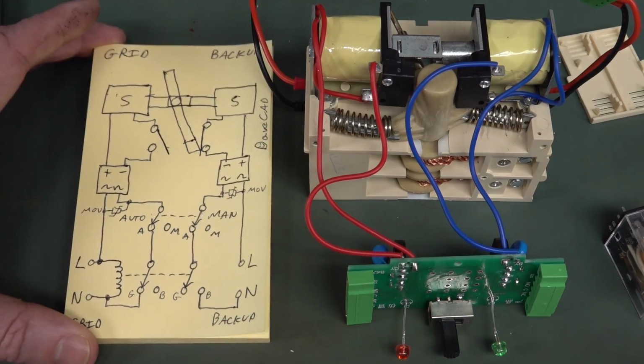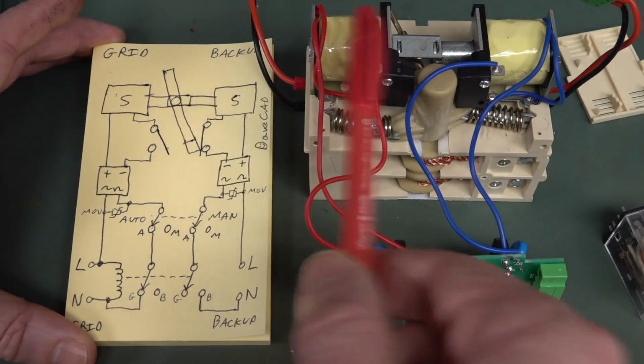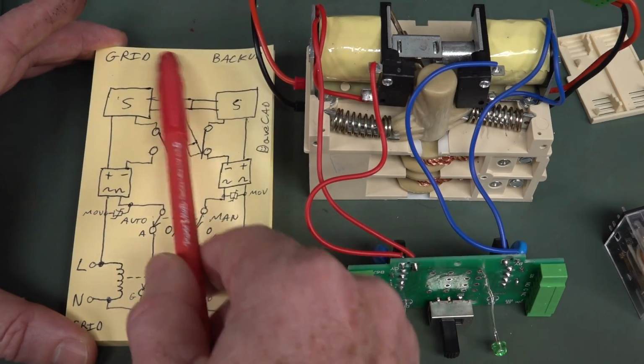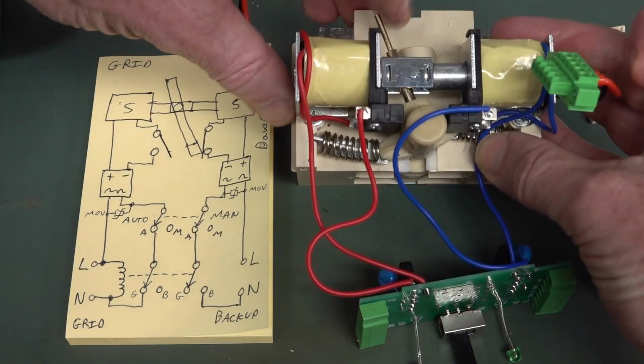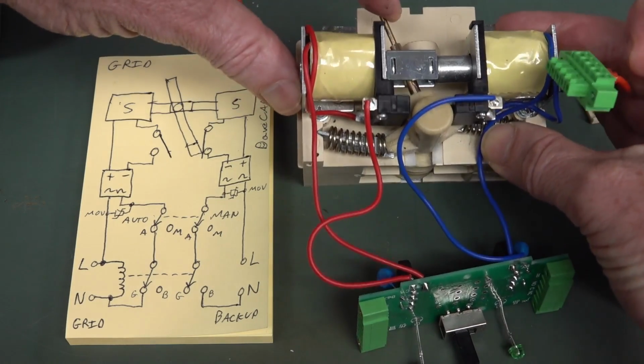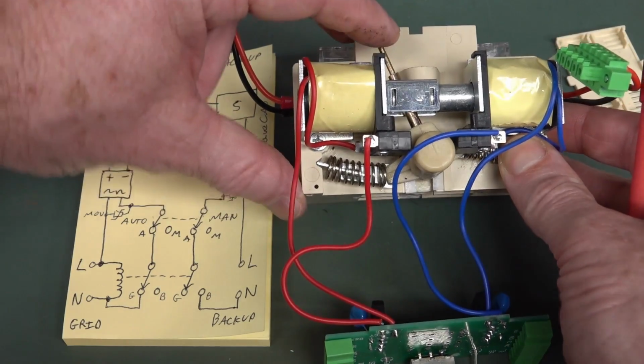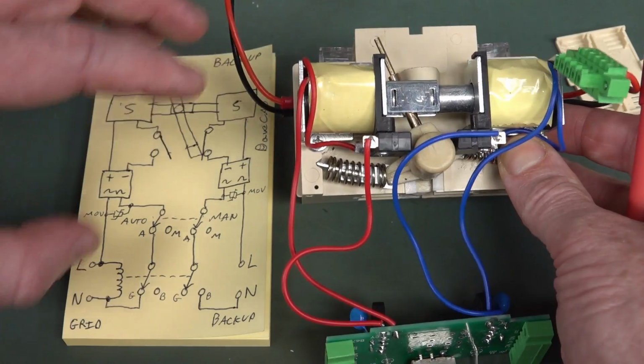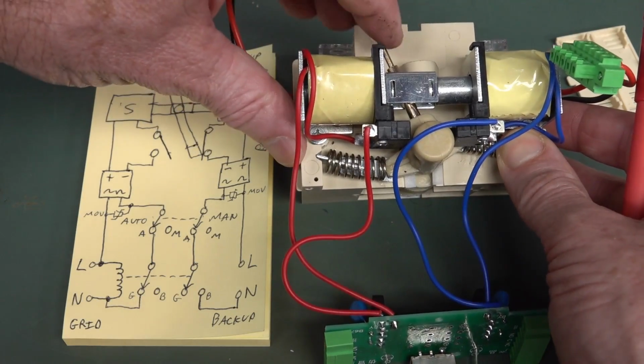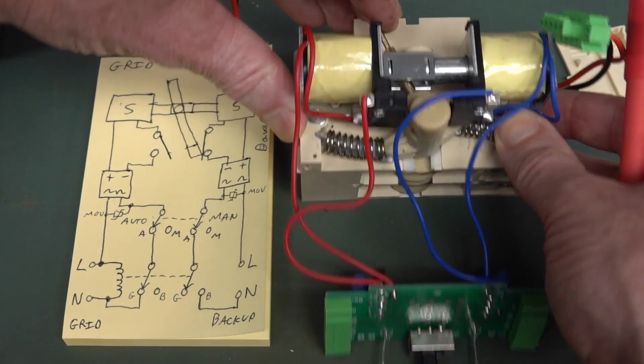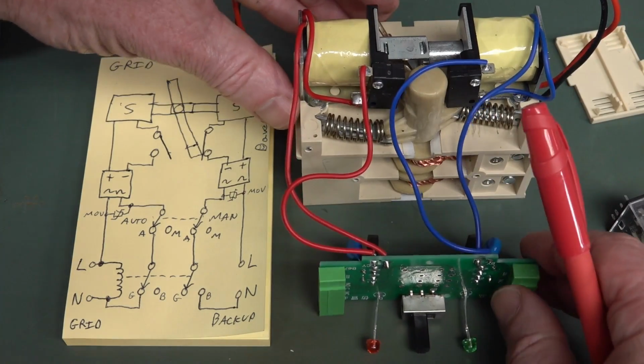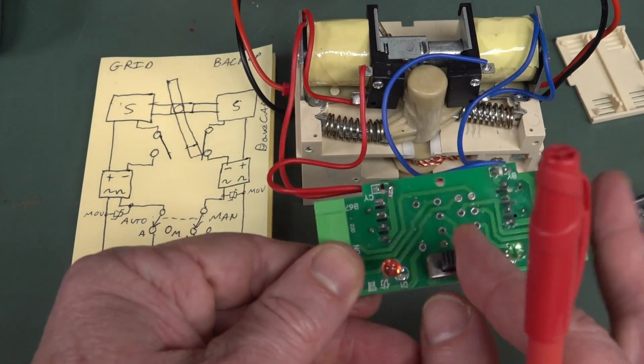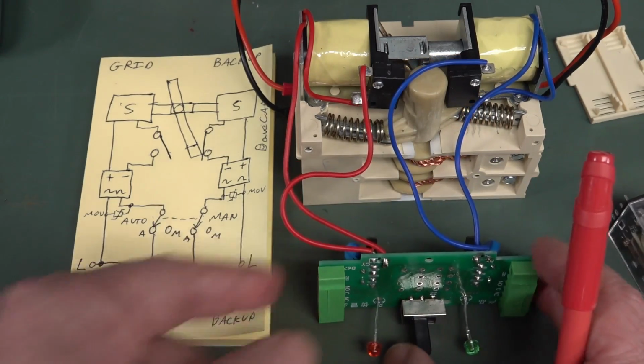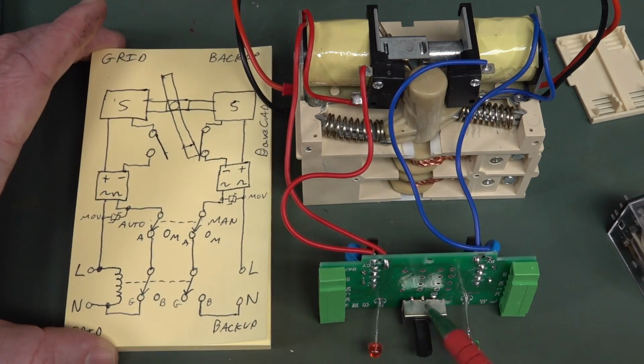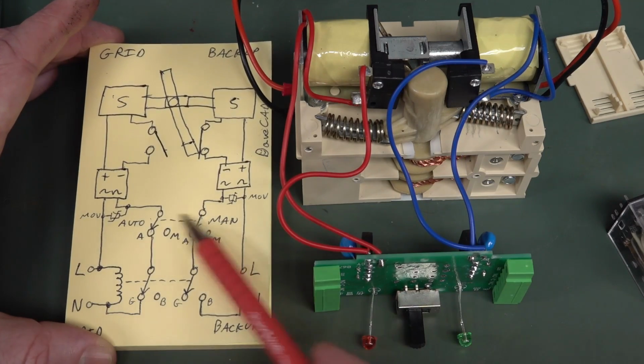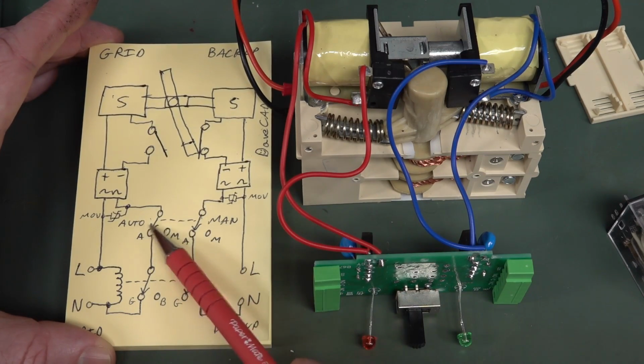I believe I've got an exact duplicate here. So we've got the two solenoids up the top here, like this, we've got the lever arm here, and I've got it in the grid position over here. So we're going to assume that we have both power connected to the grid and to the backup as well, and our switch is physically in the grid position. So it's all operational, it's powered up, and we're going to assume our switch is in automatic mode as well. I've shown this auto manual switch here as this switch here, so I've put it in auto mode.